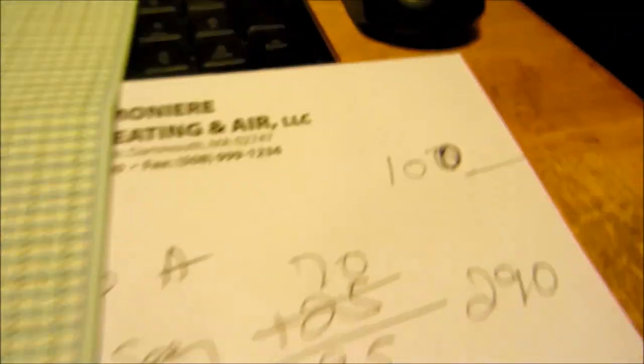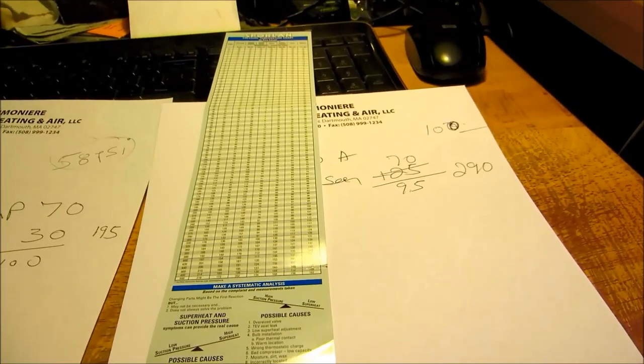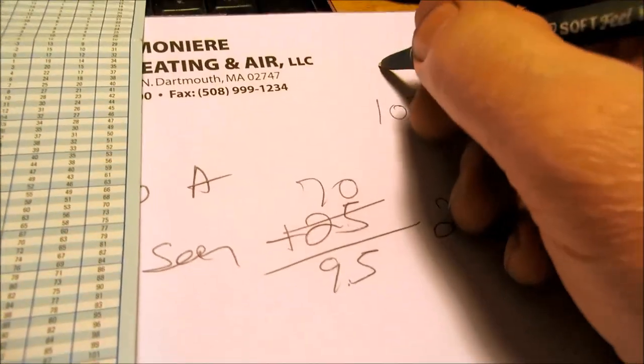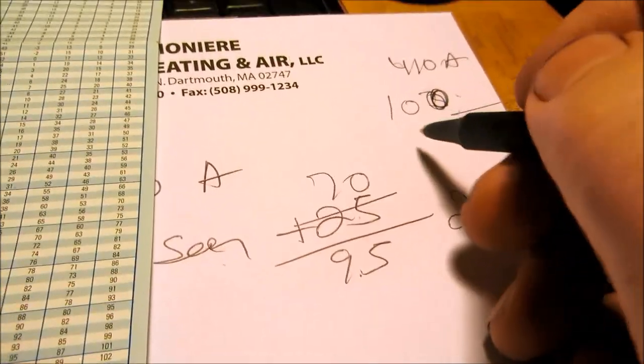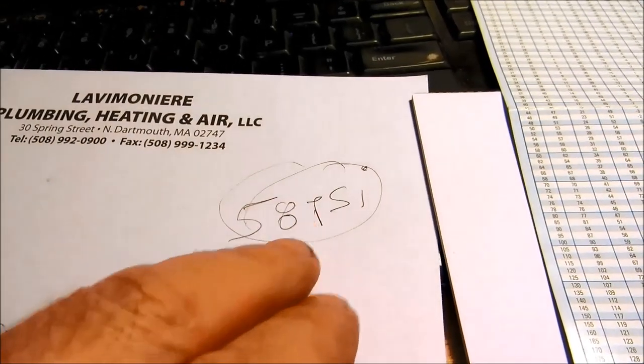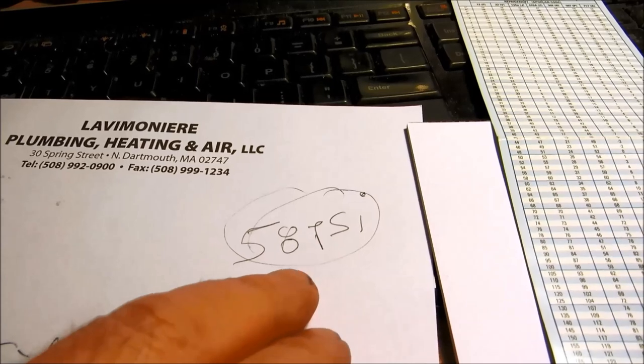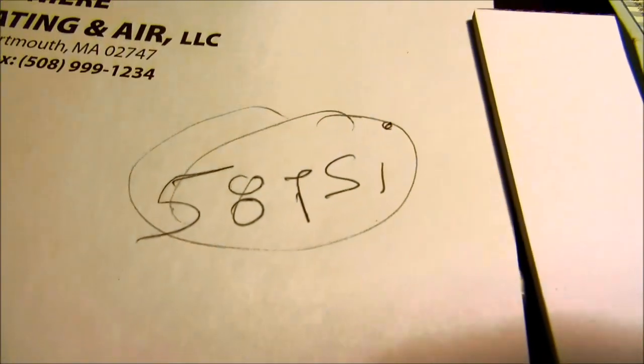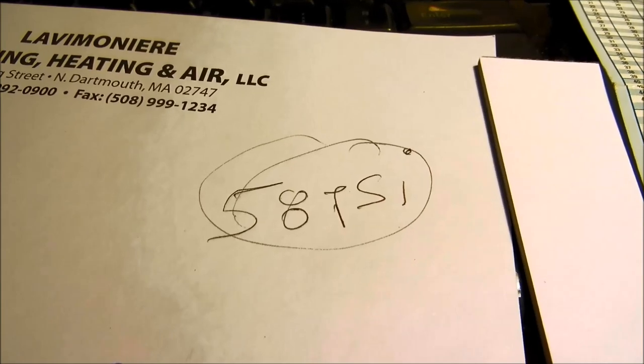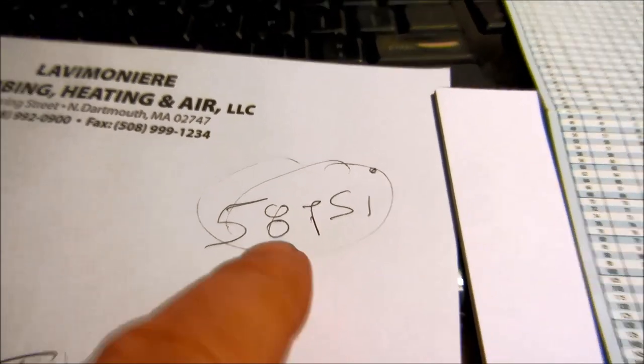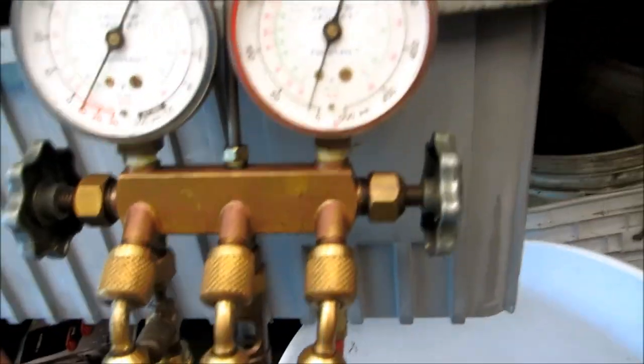This is the temperature pressure chart on 410a. 31 degrees is 100 PSI. I always say anything below 100 you really need to be concerned about. You might have an airflow problem or could be low on charge. That's the suction pressure you want to be above. Usually it's 110 to 120 on the suction pressure.